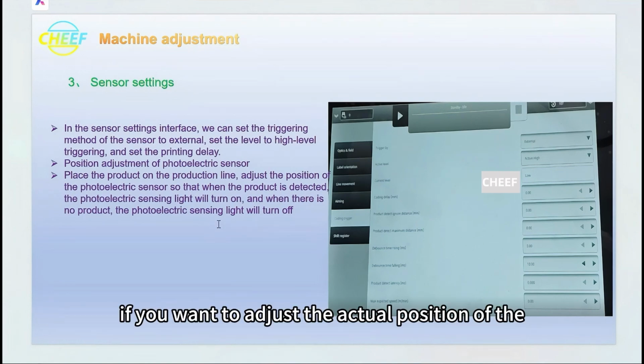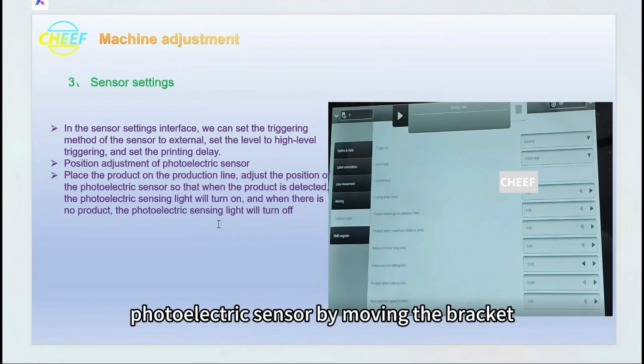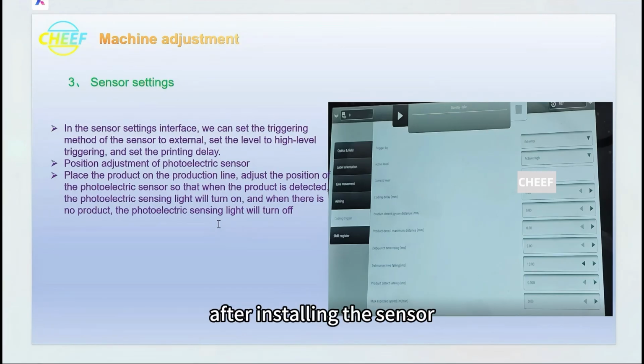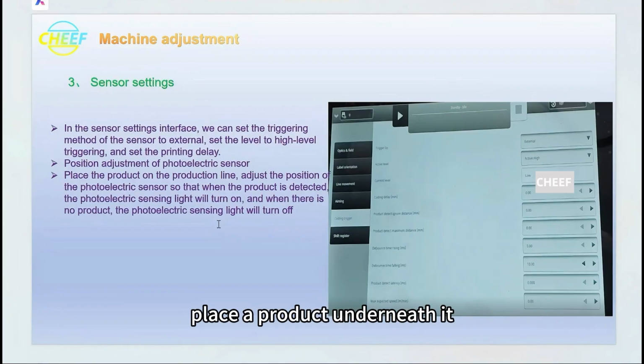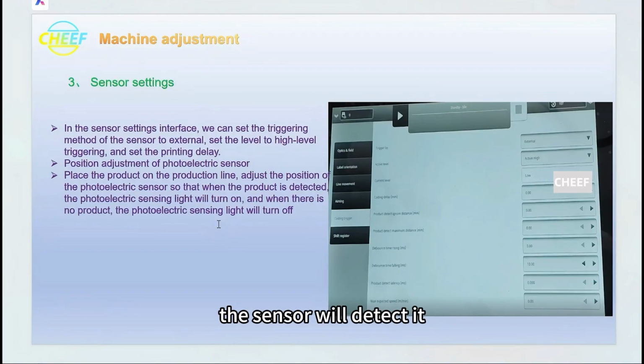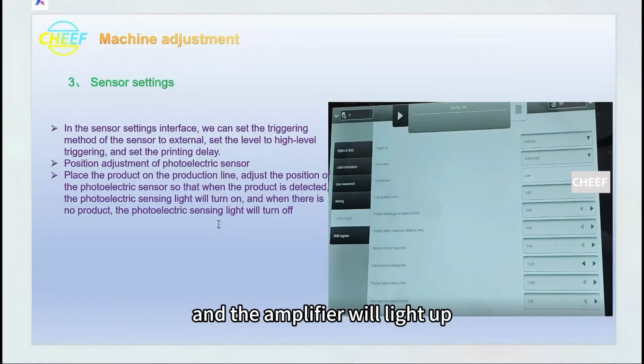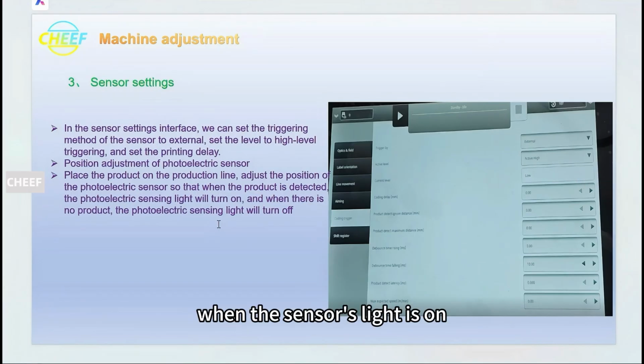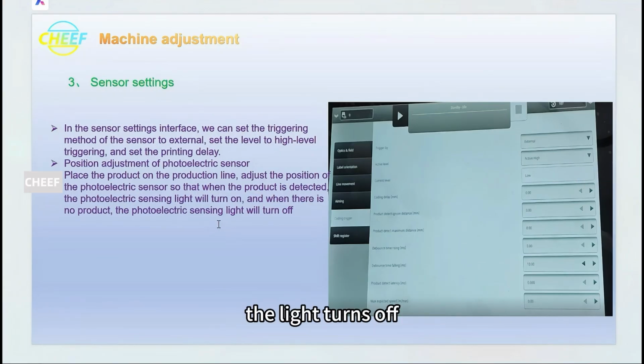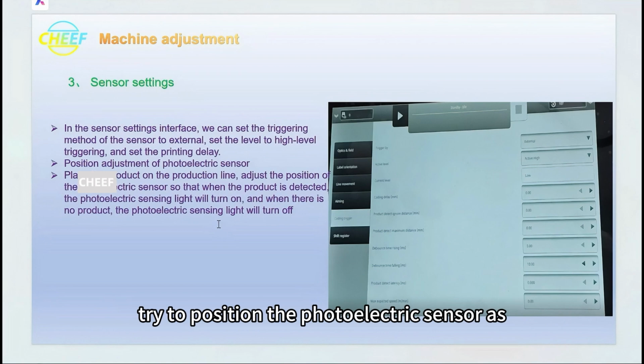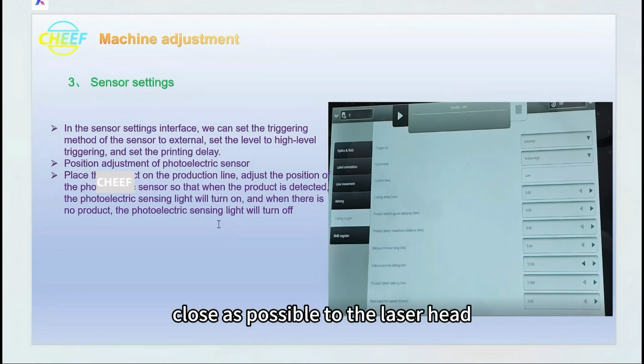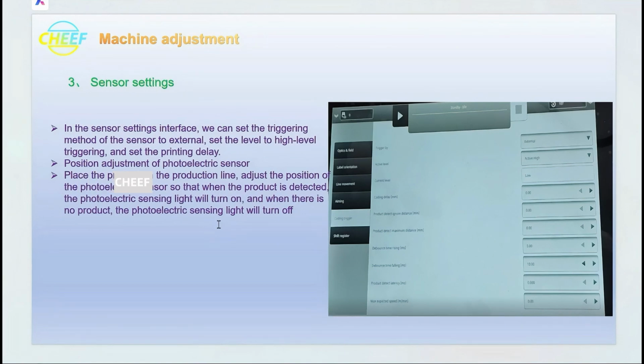If you want to adjust the actual position of the photoelectric sensor by moving the bracket, you can do so as well. After installing the sensor, place a product underneath it. When a product passes by, the sensor will detect it, and the amplifier will light up. When the sensor's light is on and we remove the product, the light turns off. Try to position the photoelectric sensor as close as possible to the laser head. This is the sensor setup.